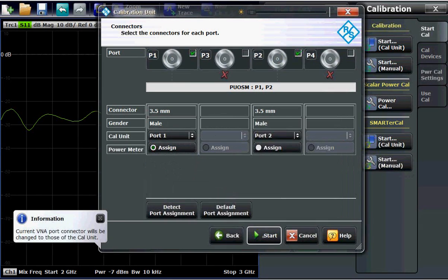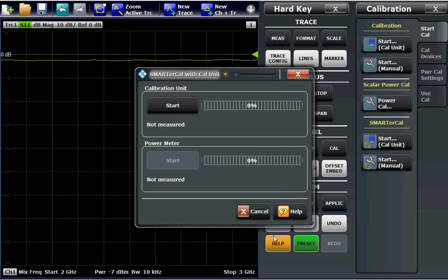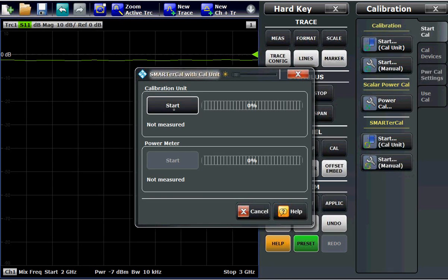In the next window, we have to tell the Smarter calibration procedure which port is assigned to the power meter, so we are choosing port number 1. Okay, for performing the system error correction calibration, we have to connect port number 1 and port number 2 to the AutoCal unit and press the Start button.